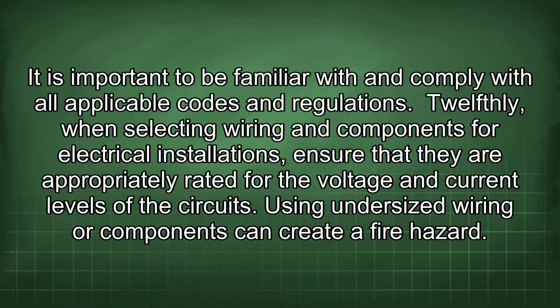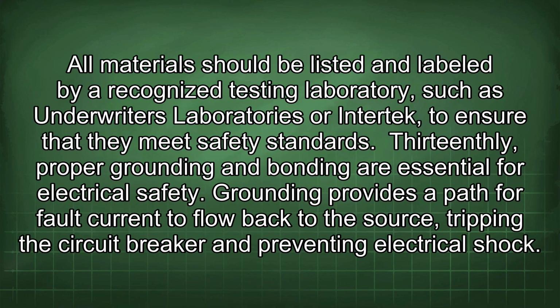12thly, when selecting wiring and components for electrical installations, ensure that they are appropriately rated for the voltage and current levels of the circuits. Using undersized wiring or components can create a fire hazard. All materials should be listed and labeled by a recognized testing laboratory such as Underwriters Laboratories or Intertek to ensure that they meet safety standards.